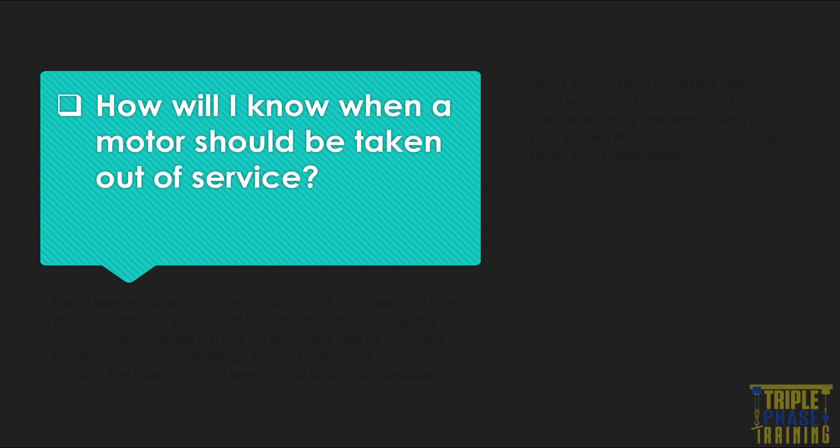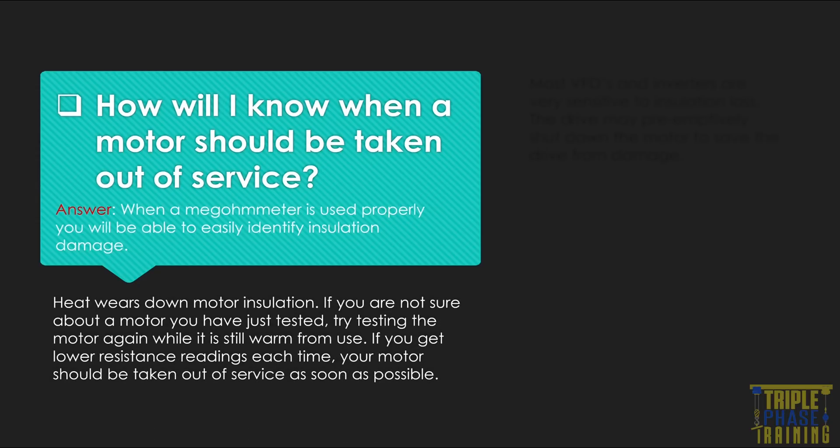How will I know when a motor should be taken out of service? When a megohmmeter is used properly, you will be able to easily identify insulation damage. Heat wears down motor insulation. If you are not sure about a motor you have just tested, try testing the motor again while it is still warm from use. If you get lower resistance readings each time, your motor should be taken out of service as soon as possible.